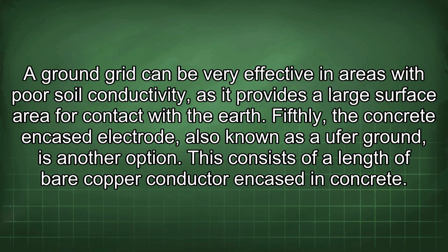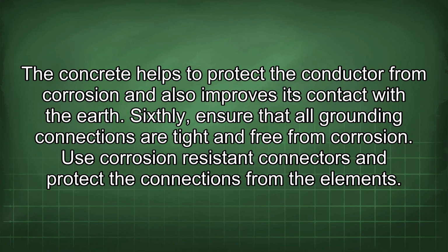Fifthly, the concrete encased electrode, also known as a Ufer ground, is another option. This consists of a length of bare copper conductor encased in concrete. The concrete helps to protect the conductor from corrosion and also improves its contact with the earth.